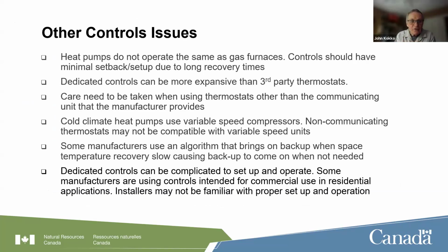Then there are some other control issues that we want to be aware of. Heat pumps don't operate the same as a gas furnace. The output temperatures are lower, capacities are lower. So one of the things is we want to have minimal setback due to long recovery times with heat pumps. So we really want to operate them with only a few degrees of setback at night or when we're away. I didn't mention it, but all of those examples were also the same in that they had no setback.